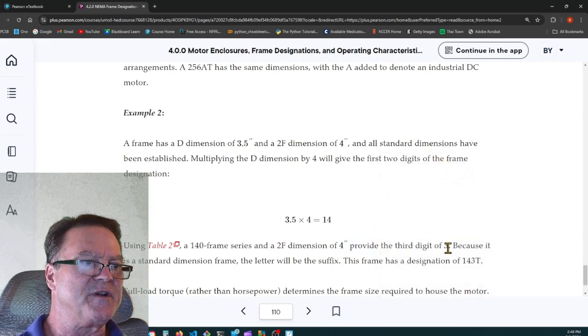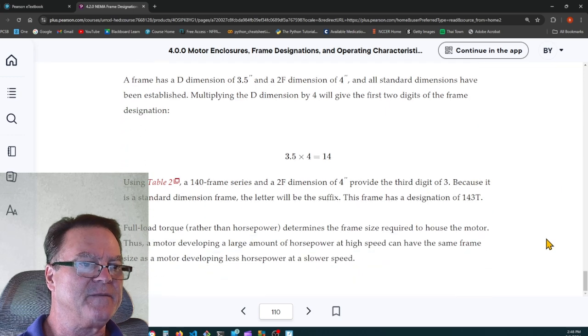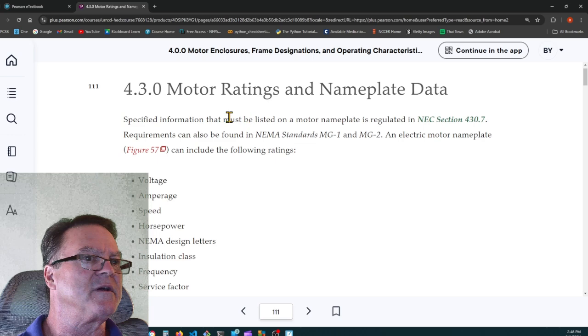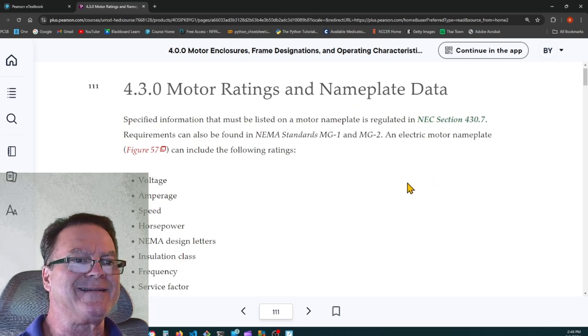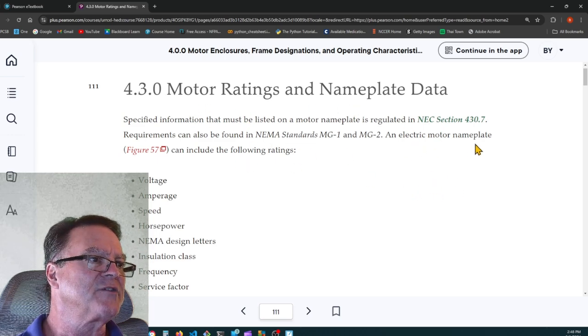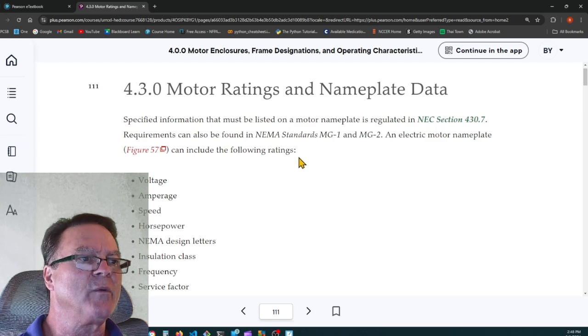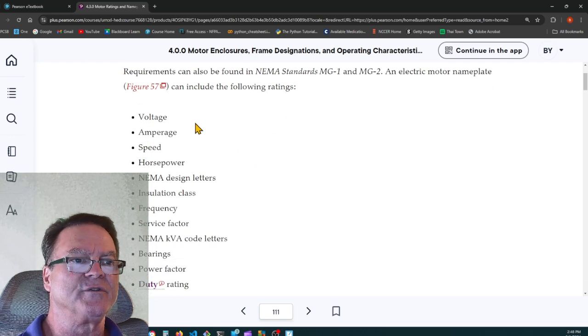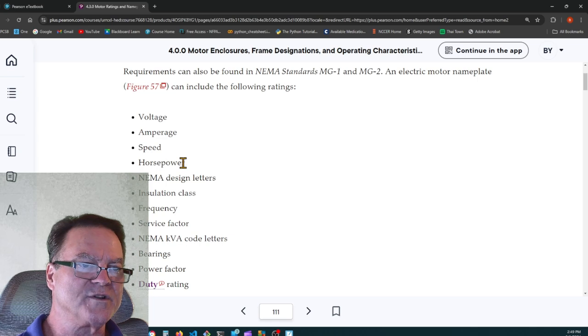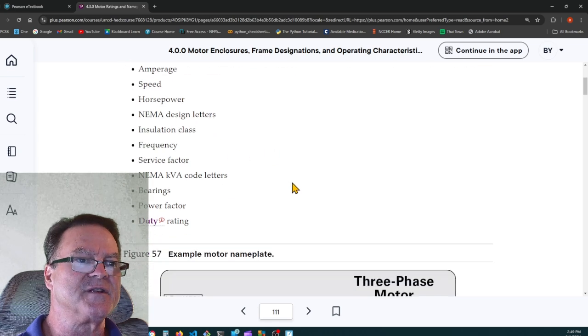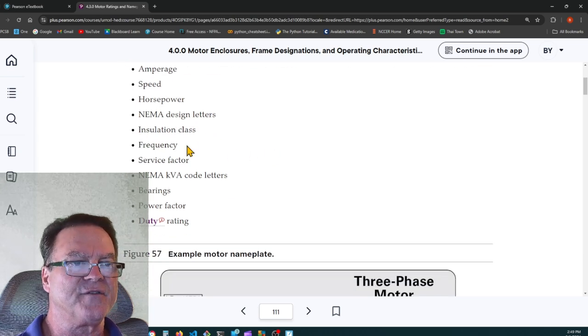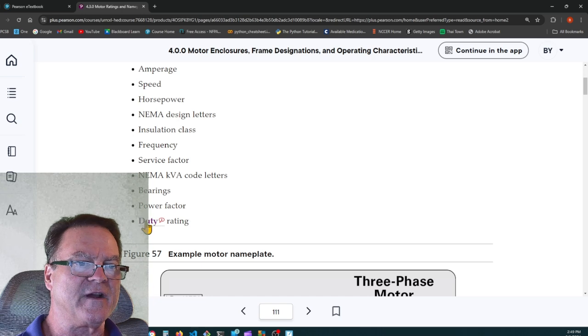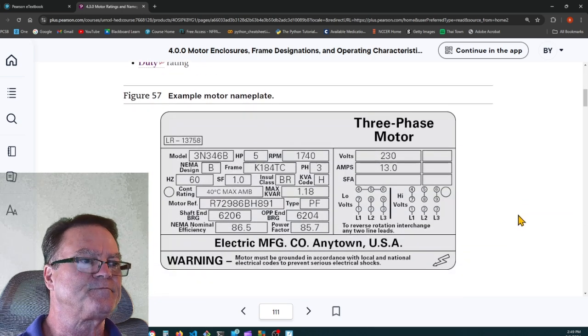The third digit is 3, so it's 143T. All right. You don't have to memorize that. Motor ratings and nameplate data. An electric motor nameplate can include the following ratings: the voltage, the amperage, the speed, the horsepower, the NEMA design letters, insulation class, frequency, service factor, NEMA kilovolt amp code letter, bearings, power factor, and the duty rating.